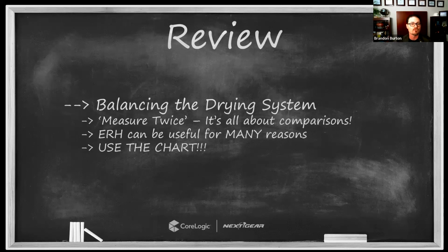It's the difference. So measure twice. The second principle I really wanted to highlight today is this measurement of equilibrium relative humidity. It's not something you're going to use all the time. Containing that hygrometer to a surface takes time, it takes acclimation, but when you're dealing with high value materials, high sensitivity materials, complex materials, or a project where there's a high sense of urgency on your drying times for whatever reason, then ERH can become a very useful tool.